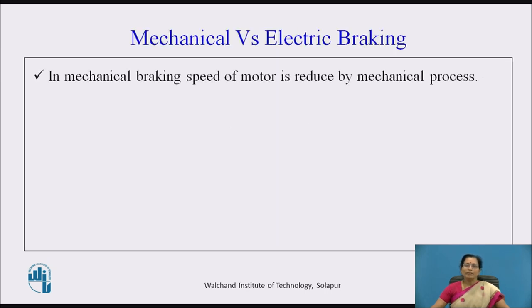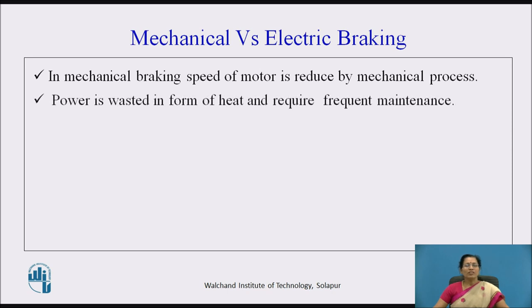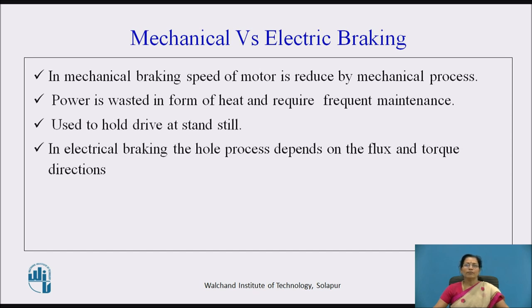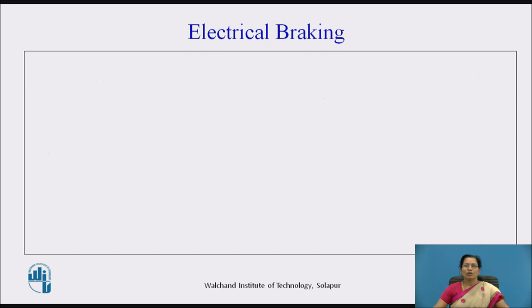In mechanical braking, the speed of the motor is reduced by a mechanical process. Power is wasted in the form of heat and it requires frequent maintenance. Mechanical braking is used to hold the drive at standstill. In electrical braking, the whole process depends on the flux and torque direction. Electrical braking allows a smooth stop.